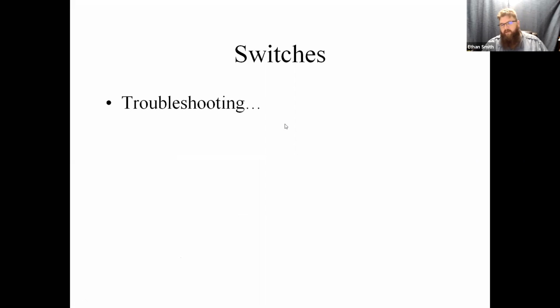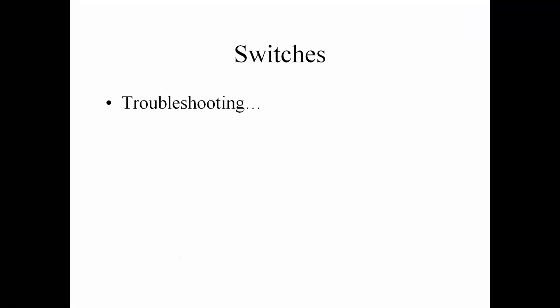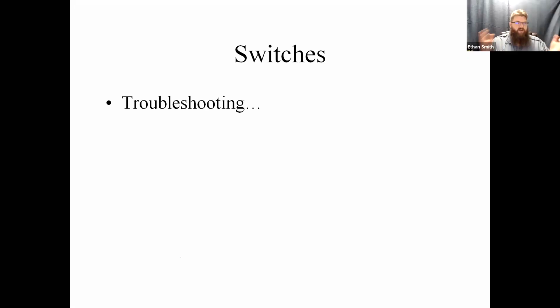Okay, so troubleshooting switches. We kind of talked about this a little bit last week, but when a closed switch is under power, what kind of voltage reading should you see across it? 0. Should be 0 volts because a closed switch, when it's energized, is just a piece of wire. It's a conductor at that point. You don't get any voltage across the switch until you open it.